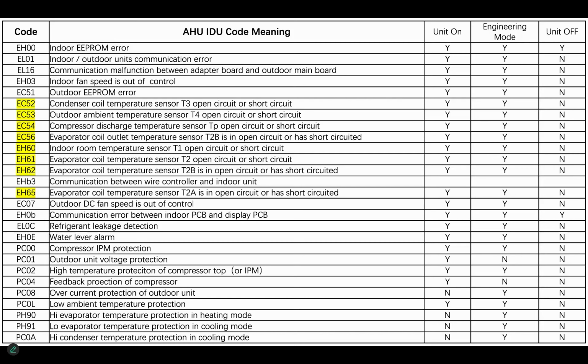Let's say, for example, TP was the problem. When it polled the sensors, the DC bus went down because of a shorted sensor. When the DC bus came back up, if it was seeing T3, that's the one that's going to show you. So don't always assume, because it says it's a T3 sensor, that it is the T3 sensor. Always check all your sensors, because it could be any of them. One of the things I would do is disconnect the sensor from the board, check that particular sensor to make sure it's good, and then check the 5-volt DC bus at the sensor with the sensor unplugged. You should see between 4.5 and 5.2 volts.